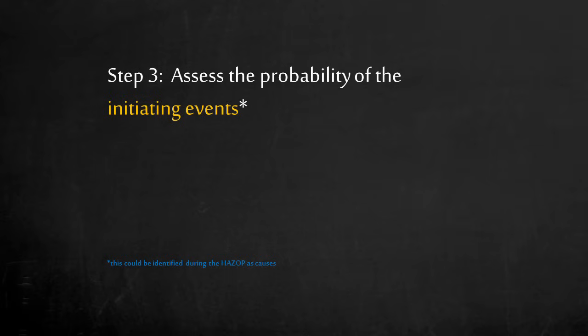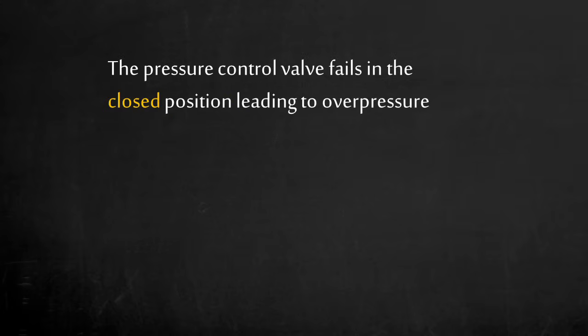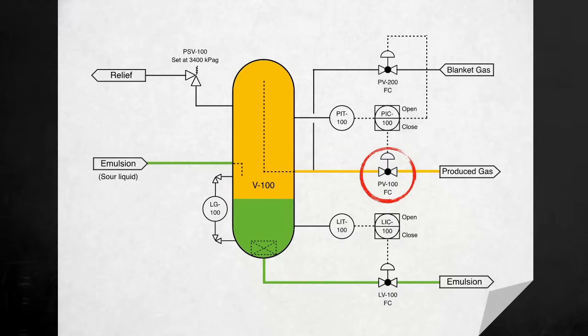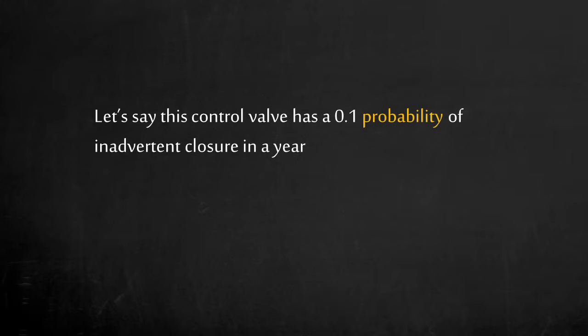Step 3: we need to determine what initiated the consequence and how likely it can happen. The cause of a deviation in a HAZOP is the initiating event in the LOPA. For our case, the initiating event is the pressure control valve failing in the closed position. There is blocked flow of the produced gas line when PV100 is closed, causing V100 to overpressure. The pressure control valve has a 0.1 probability of failing closed in a year — or once in 10 years.